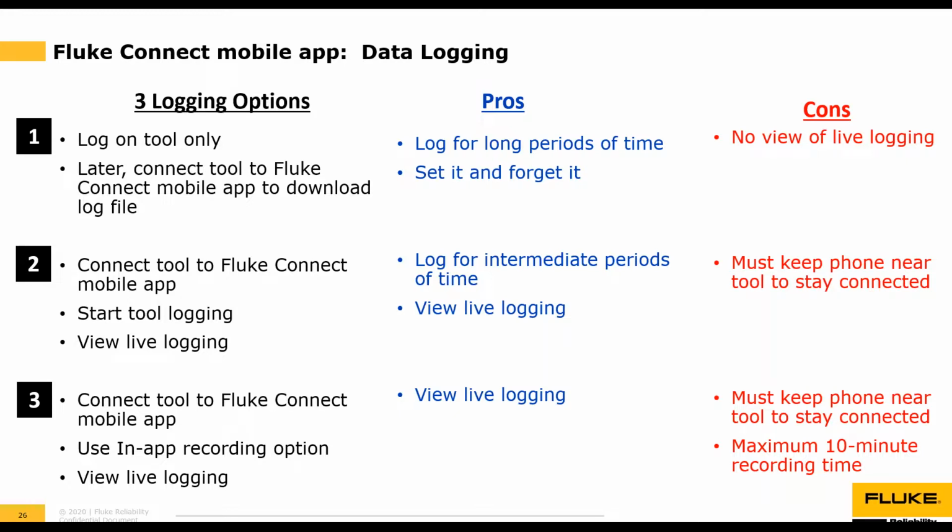So the pros for option number one are that you can log data for a long period of time. In some cases, this can be a 24-hour period. The length of time you can log is only limited to the amount of memory or space on the tool itself and the battery life. Many tools can log up to 64,000 readings too. So depending upon how you set up the measurement interval, you can have a fairly long file.